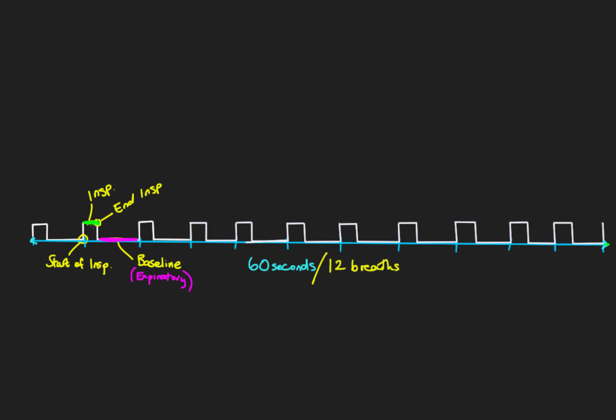With twelve breaths in our sixty-second period, we can talk about a total cycle time. Total cycle time is how long the entire breath takes — not just the inspiration phase, but the whole phase from the start of one breath to the start of the next. If we have twelve breaths per minute, sixty divided by twelve gives us a total cycle time of five seconds per breath.